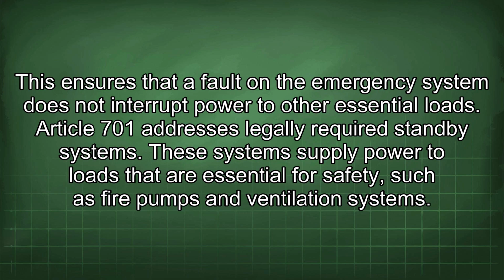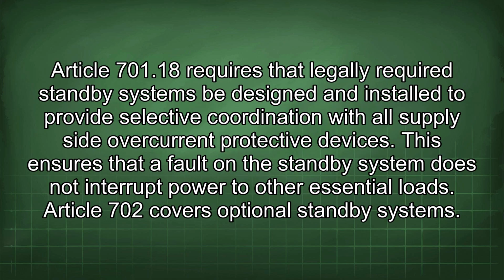Article 701 addresses legally required standby systems. These systems supply power to loads that are essential for safety, such as fire pumps and ventilation systems. Article 701.18 requires that legally required standby systems be designed and installed to provide selective coordination with all supply-side overcurrent protective devices. This ensures that a fault in the standby system does not interrupt power to other essential loads.